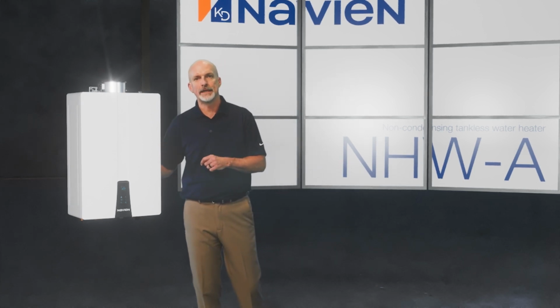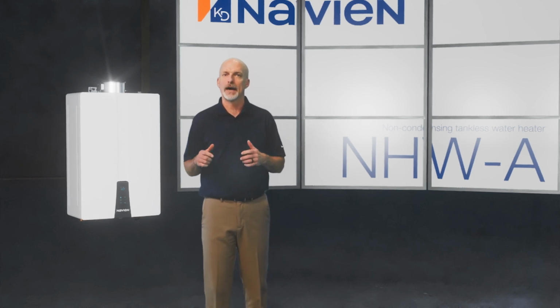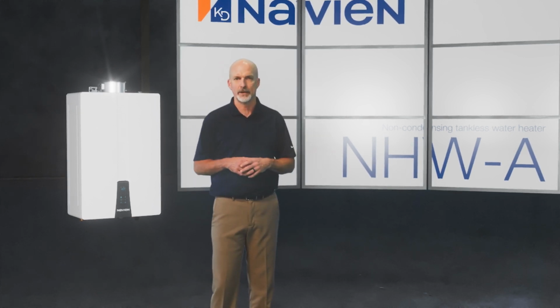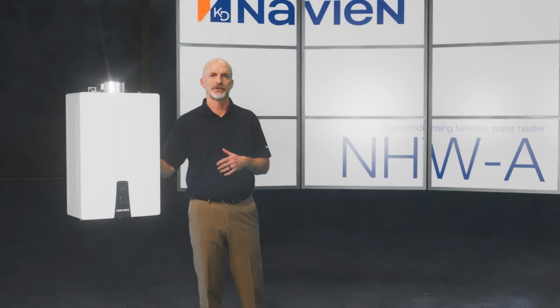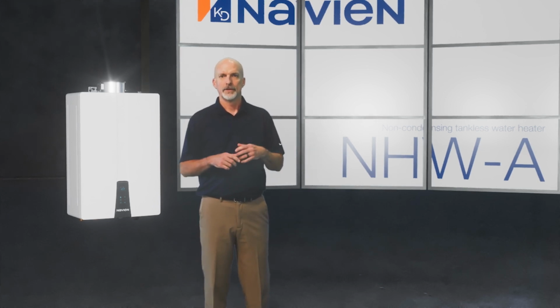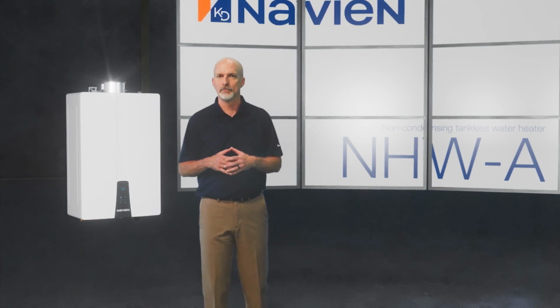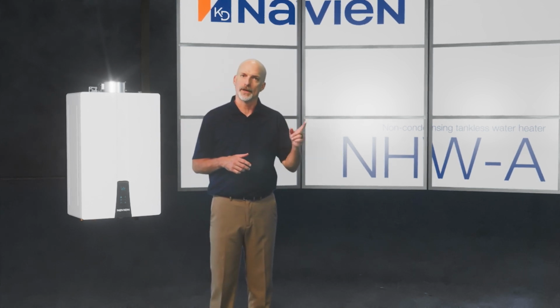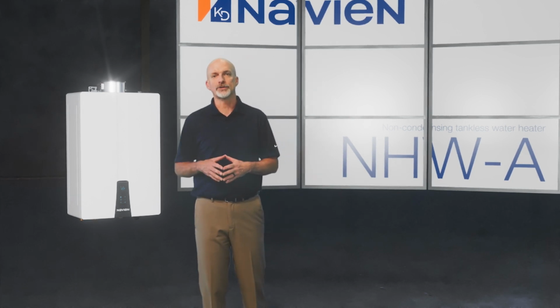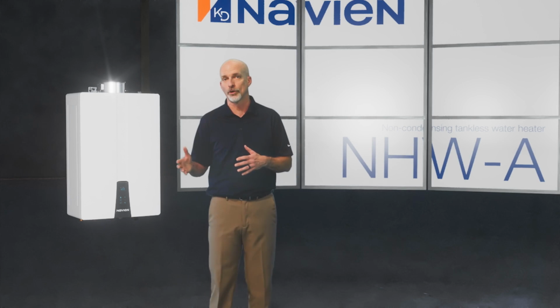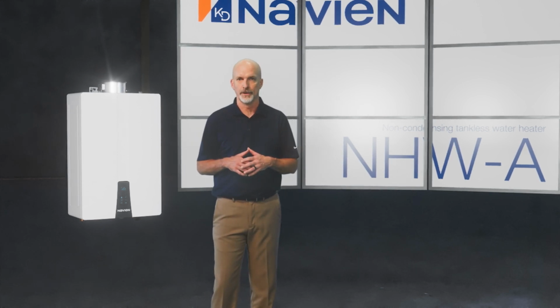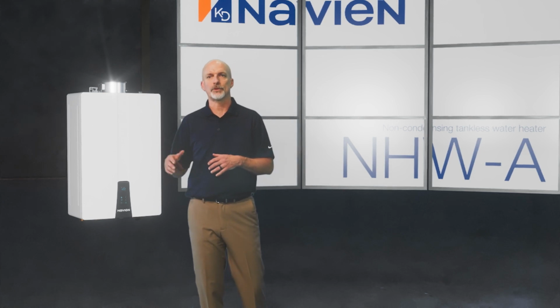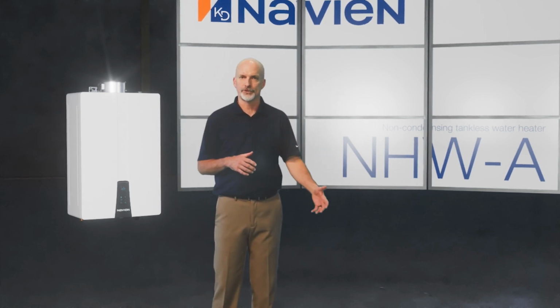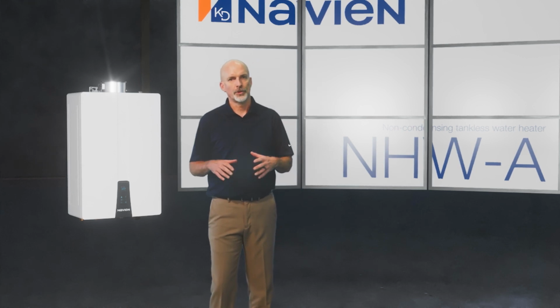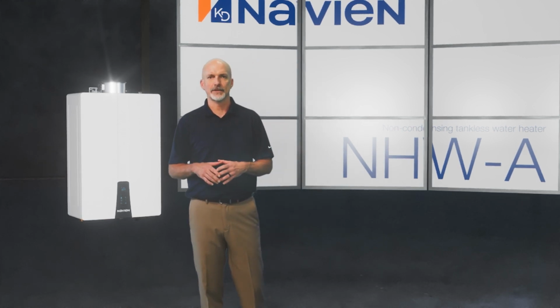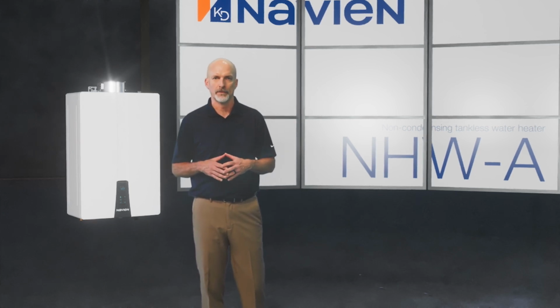Using the intelligent preheating option means the water heater will learn the hot water use of the house over a 7-day period and will operate the recirculation system based on that pattern. This technology has been part of the Navien lineup since the introduction of the NPE in 2012. A 24-hour schedule can be set up using the Navien remote controller, which is included with the exterior unit. The hot button control accessory can also be added if an on-demand recirculation control is needed. With all these options, the NHW Advanced Tankless Water Heater will match any system requirement.